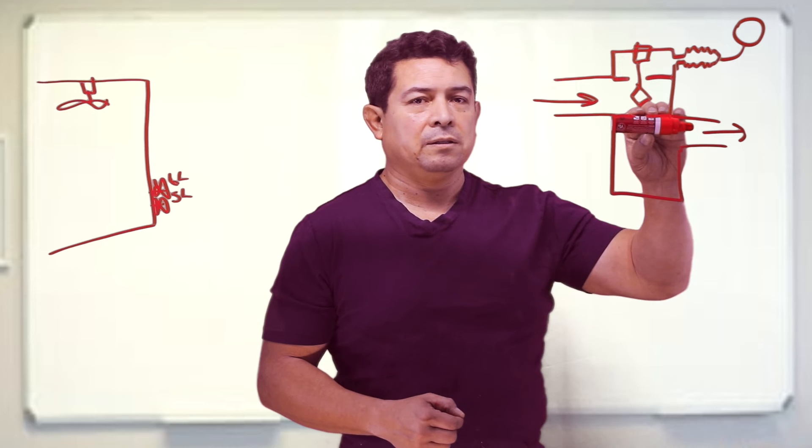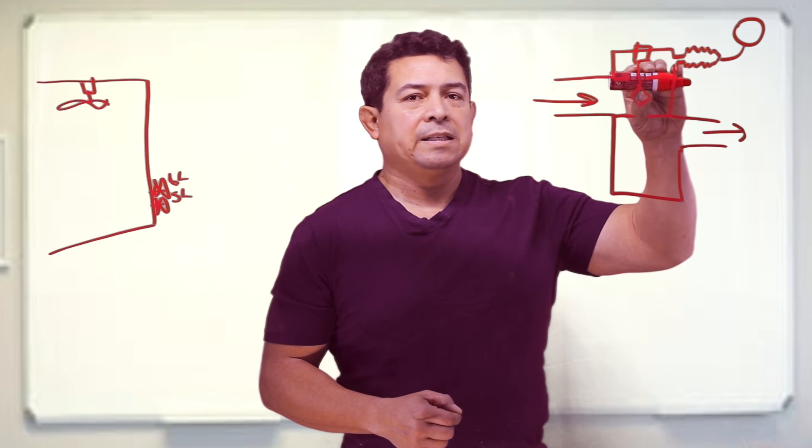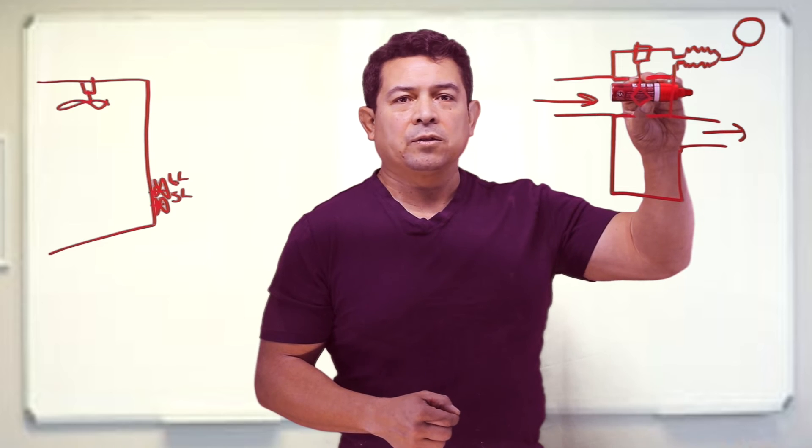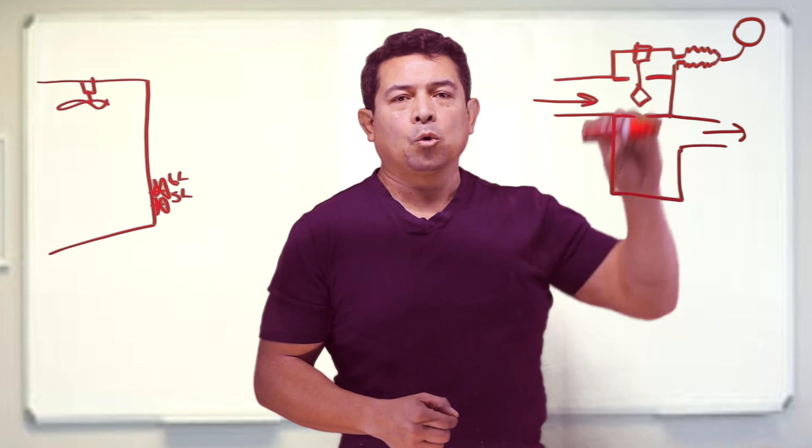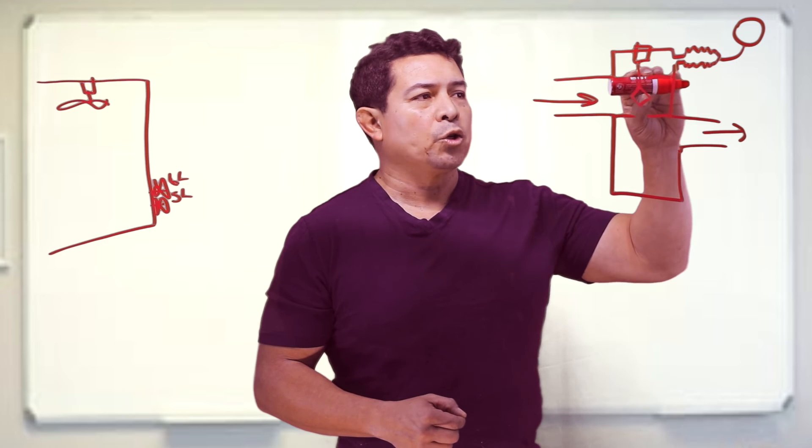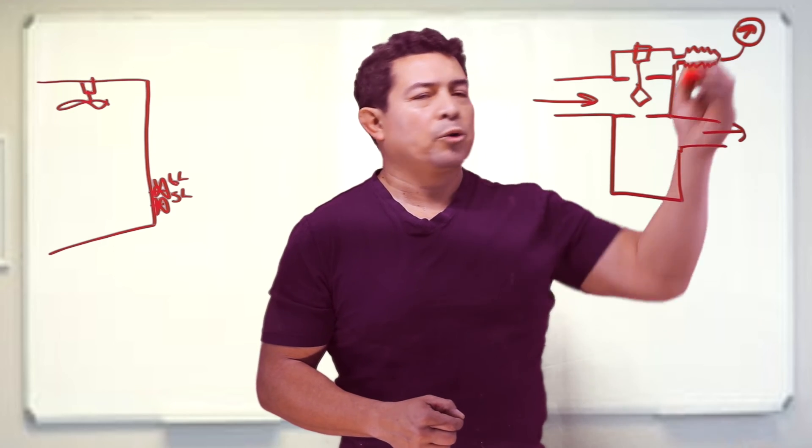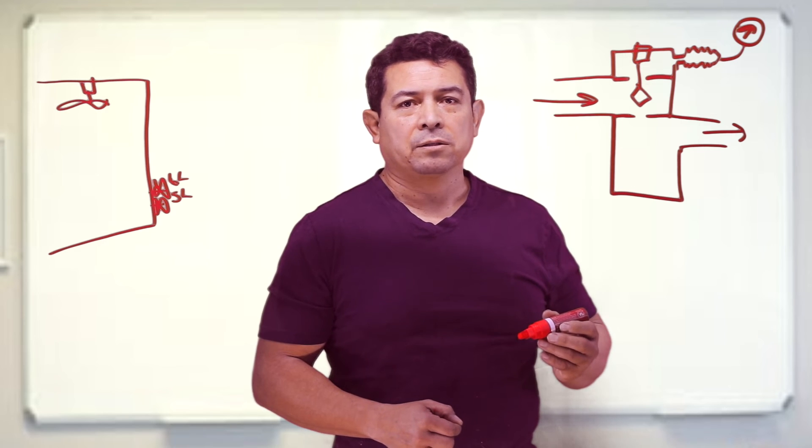So again this will be front seated, this will be back seated, and if it's just off of this then that's going to be your mid position or your cracked. You want it to be cracked or you want it to be mid position so that we can get an actual pressure reading on your gauge right there.